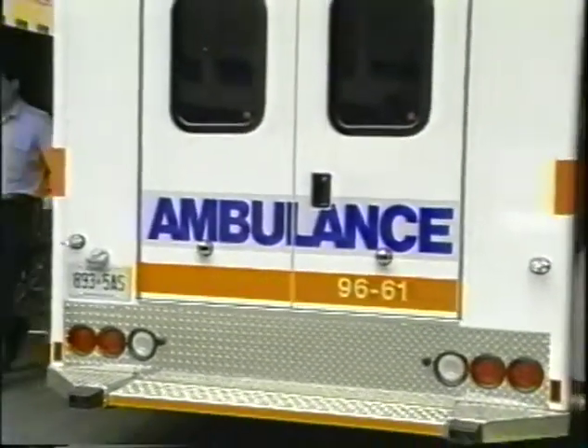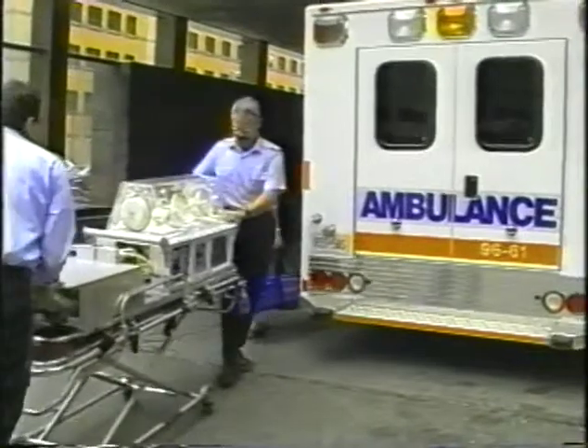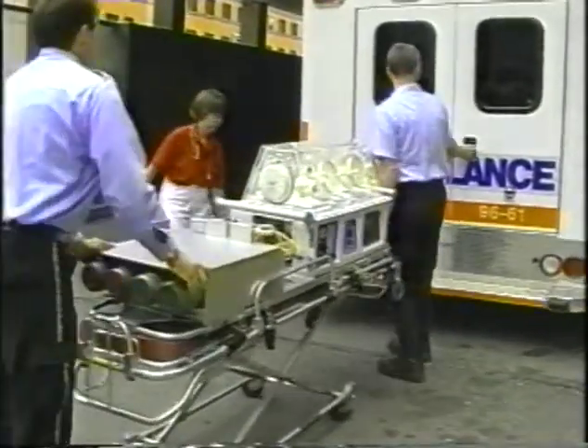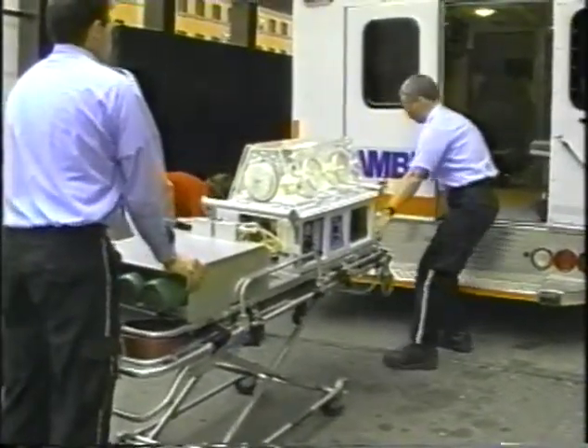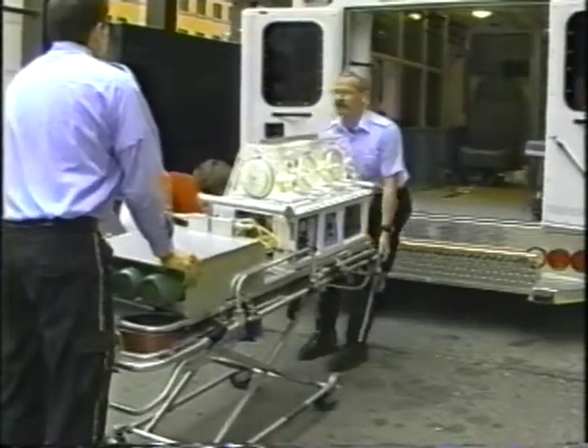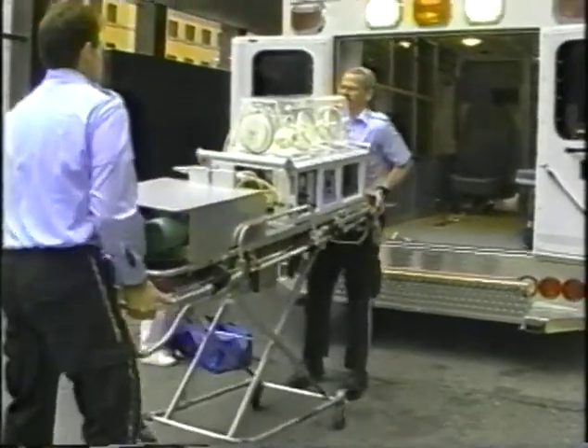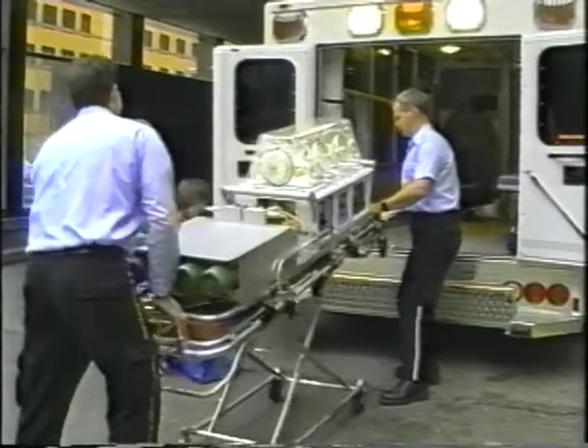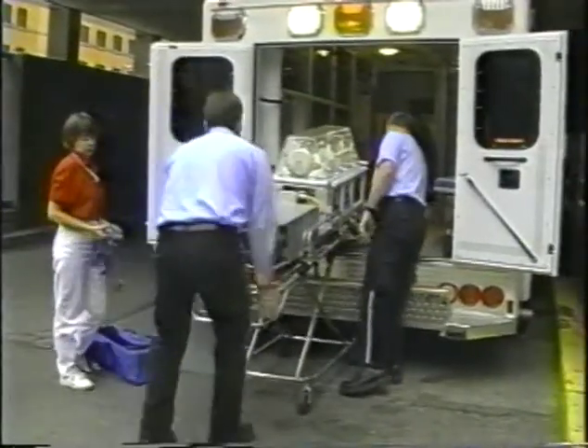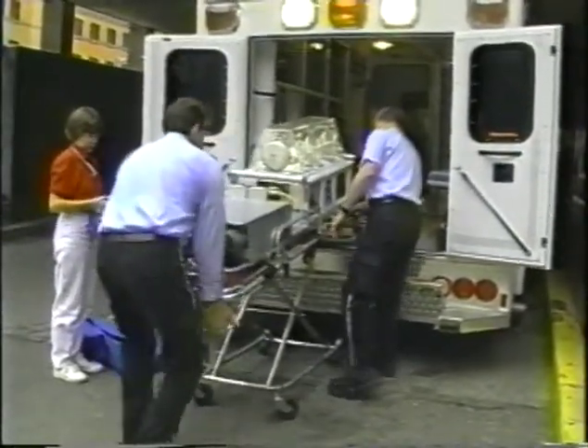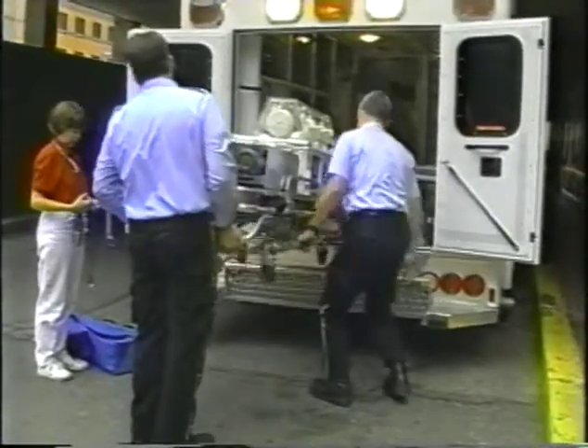There should never be less than 2 paramedics in contact with the stretcher-incubator combination at all times during movement. Ensure the leg carrying pouch accompanies the incubator deck. Ready, set, lift. At the ambulance, adjust the height of the stretcher-incubator combination to a loading height of 7 or 8. Load in the usual manner.